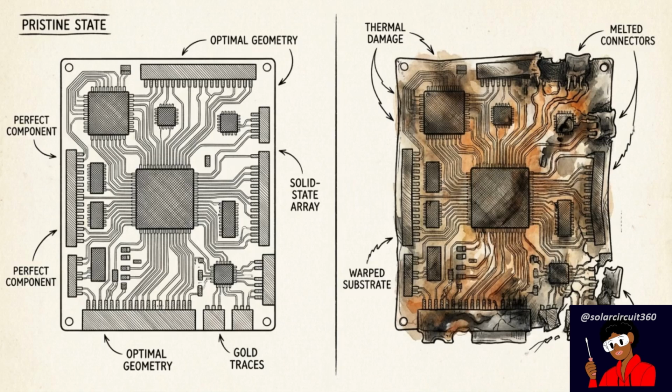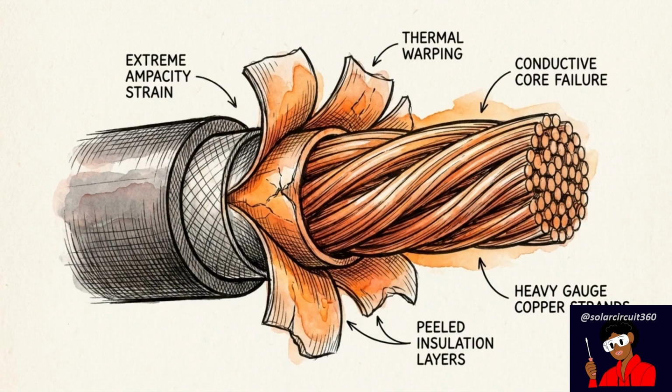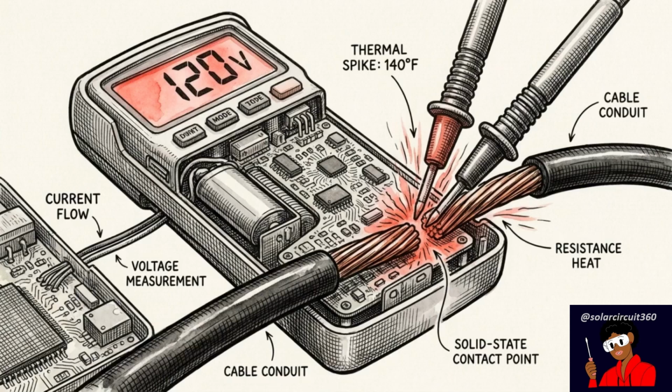Operating continuously at the thermal ceiling accelerates component degradation. It severely reduces the lifespan of the inverter. There are also strict overcurrent risks if you oversize an array without properly calculating the MPPT current limits. Excessive DC input strains the cable ampacity, which can compromise the physical integrity of your system's wiring. Excessive oversizing shifts the system from a predictable efficiency trade-off to a configuration that risks localized overheating and accelerated component failure. Clipping is a measurable active intervention with strict thermal consequences.